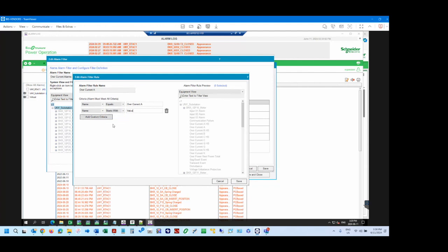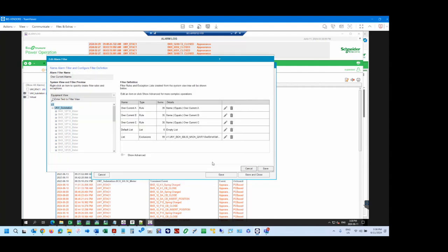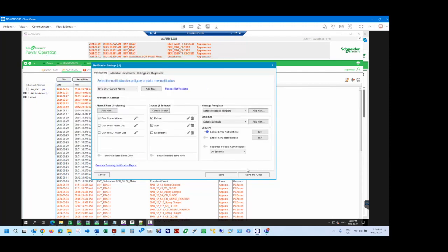Another example is this is looking for our tag, but we don't want the tag. We want to evaluate that tag. Yeah, because we're still running the two servers. The other one's running legacy stuff, and we've got an interesting alarm that we have now that's set for power factor. So if our power factor goes below a certain level, after a certain period of time, I think it's set for 30 minutes, I can't remember, it will send us an alarm or an email or event notification. How do I do something like that? Is that, again, an ION Setup or Designer thing?